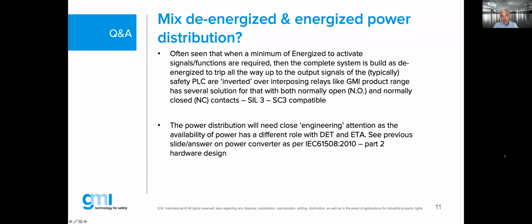Well, again, by not coincidence, that was already in our slides before in the webinar. As I said, it's very common practice that engineers will start to mix those. Nothing wrong with that, but when they mix, let's just stay on the safety PLC first. If you stay with the safety PLC de-energized to trip digital output modules, the functionality from de-energized to trip to energized to power is often being inverted by the interposer relay, which I already showed you in one of the slides of the webinars. And it makes sense to think about that.